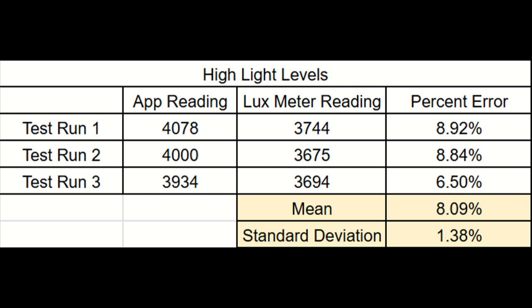Since these higher light levels, such as those in a greenhouse, are what we aim to measure, we included a clause in our specification that our error will be within 10% only above a certain lux threshold. As we can see from this table, our specification has been met for our white light sensor.